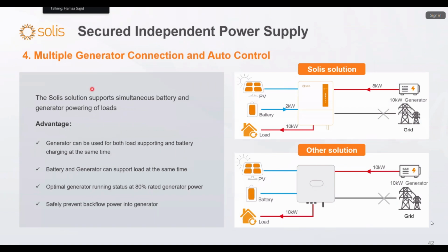Multiple generator connection and auto control system. The Solis solution supports simultaneous battery and generator powering of the load. Advantage: the generator can be used for both load supporting and battery charging at the same time. You can see the power is 8 kilowatt and 2 kilowatt is supporting the load, so together they are supporting the 10 kilowatt load. The generator can also charge up the battery and support the load at the same time. Battery and generator can support the load together. Optimal generator running status is at 80% of rated generator power.